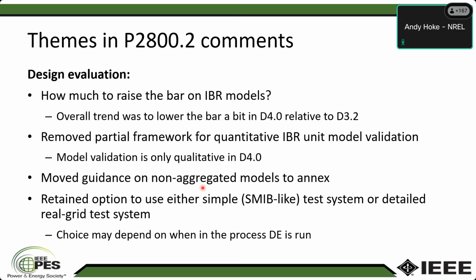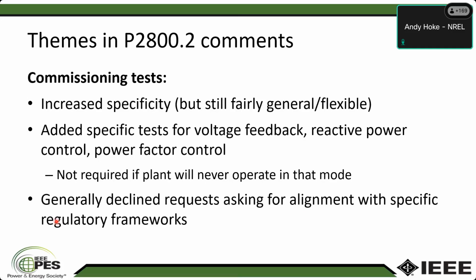And then there was some discussion about what sort of test system to use. Do we want to use a simple test system or a more detailed test system that represents the real grid where the IBR will be connected? That choice is still in there, and it's basically left up to the user to pick which of those makes sense for each case. Commissioning tests, I would say, went in a similar direction to the type tests, where there's somewhat more specificity now. We added specific tests, for example, for voltage feedback, reactive power control, and power factor control that weren't in there before.